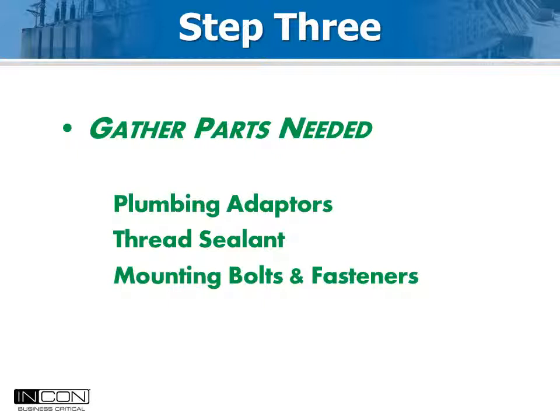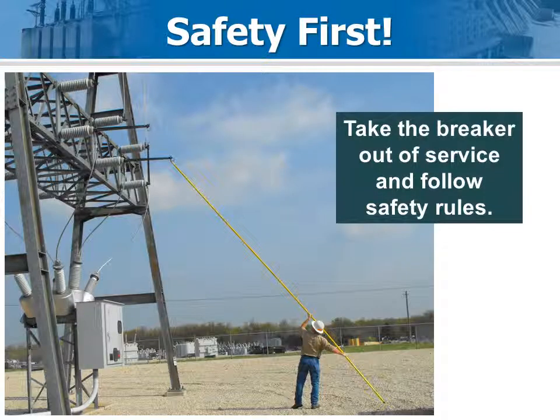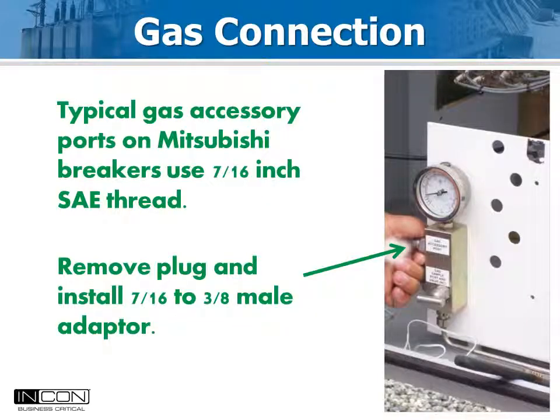When needed, Dow 111 silicone sealant is recommended for threads. Schedule the outage in advance so things go smoothly. If the crew shows up prepared with all the parts, installation generally takes less than two hours. Depending on the vintage and the model of the circuit breaker, specific gas connections vary. If you give Mitsubishi the breaker serial number, they can tell you exactly what the options and thread sizes are in advance.